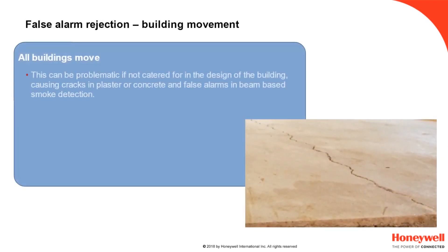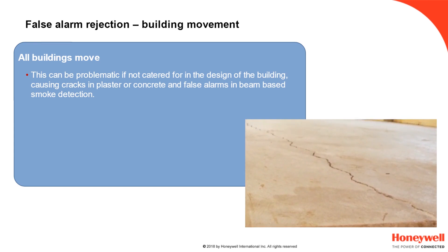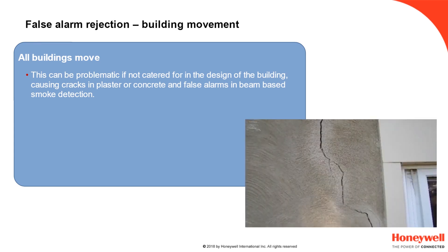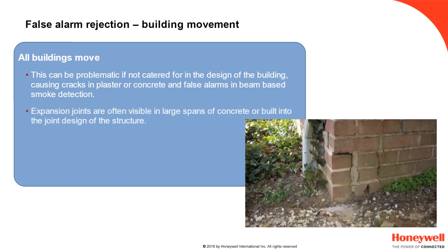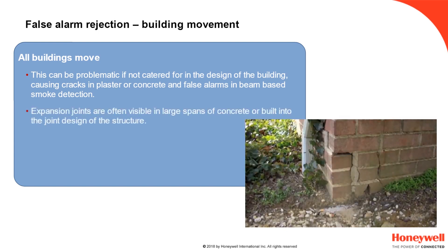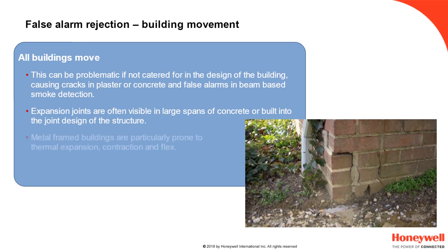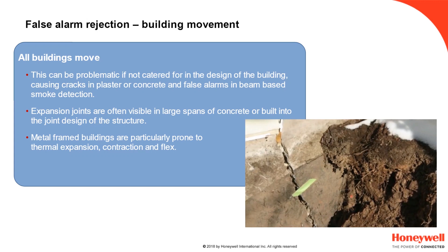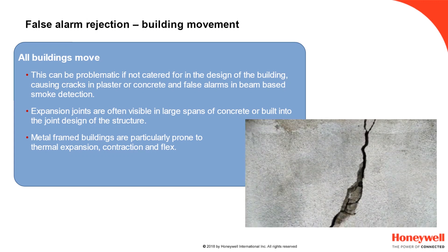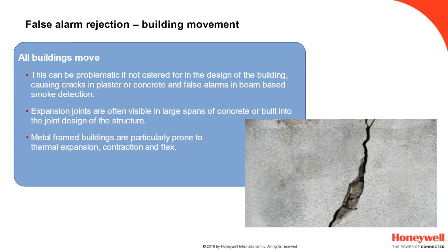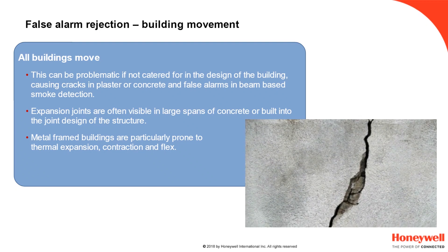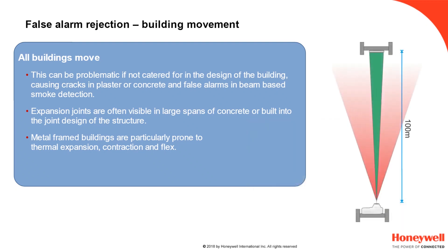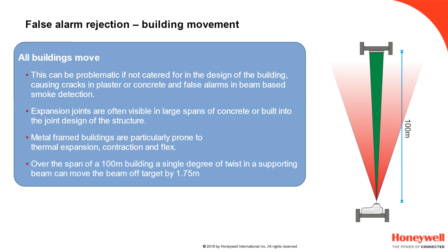False alarm rejection — building movement. Building movement is a major headache for traditional beam detectors. All buildings will be susceptible to movement, and most large buildings include expansion joints to account for this movement without stressing the fabric of the building. Metal-framed buildings, often used as the construction technique for factories and warehouses, are particularly prone to thermal expansion, contraction and twist. A small 1-degree twist in the roof beam to which the detector is mounted will move the centre point of the beam over 1.75 metres where it hits the reflector 100 metres away.